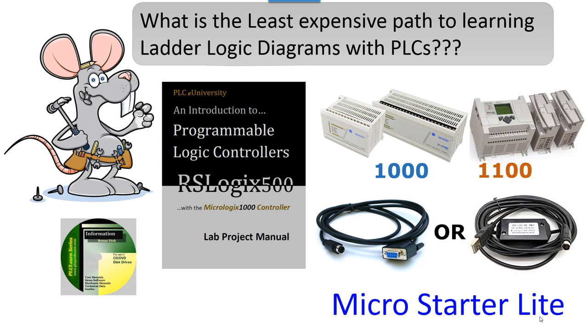Another thing to consider if you don't already own hardware: you want a controller that uses 24 volts DC to power it. You can use one that requires 115 volts AC, meaning you'd connect a line cord directly from your wall outlet — but these aren't necessarily finger-safe. A 24-volt DC wall wart power supply from eBay or Amazon for about $12, combined with a controller that uses 24 volts rather than 115, is the safest and best approach.